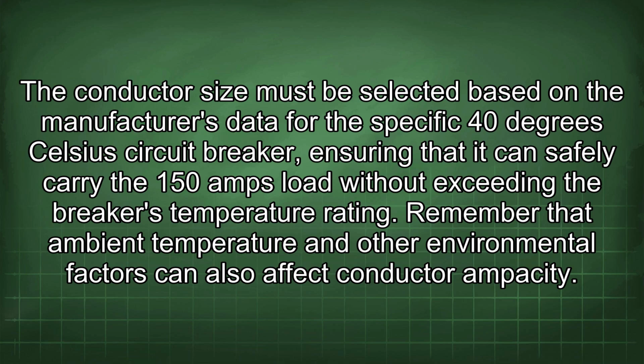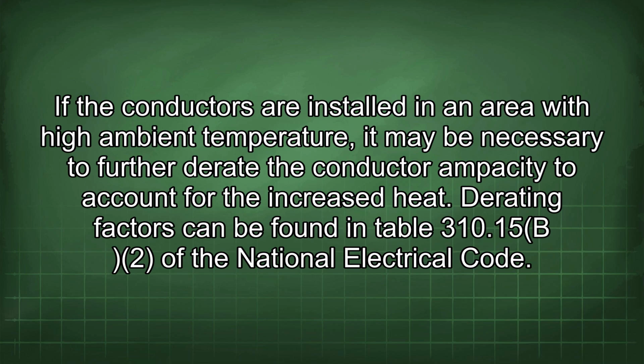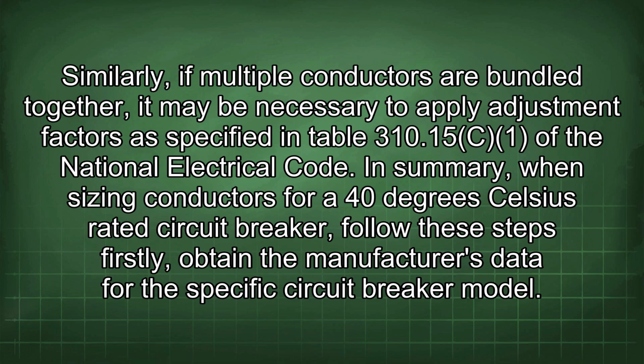Remember that ambient temperature and other environmental factors can also affect conductor ampacity. If the conductors are installed in an area with high ambient temperature, it may be necessary to further derate the conductor ampacity to account for the increased heat. Derating factors can be found in Table 310.15(B)(2) of the National Electrical Code. Similarly, if multiple conductors are bundled together, it may be necessary to apply adjustment factors as specified in Table 310.15(C)(1) of the National Electrical Code.